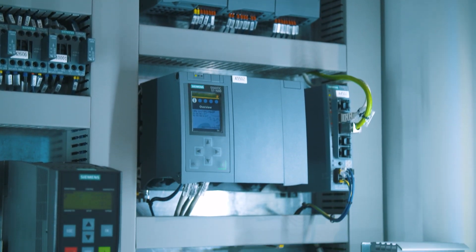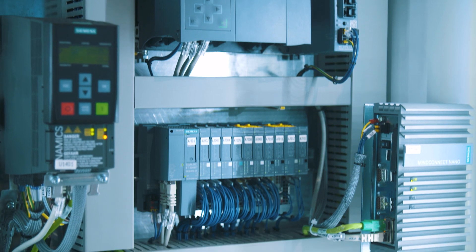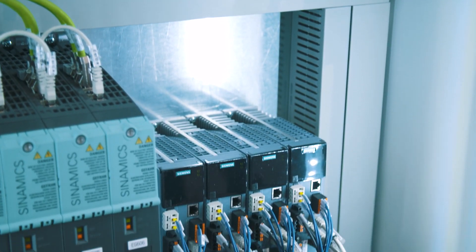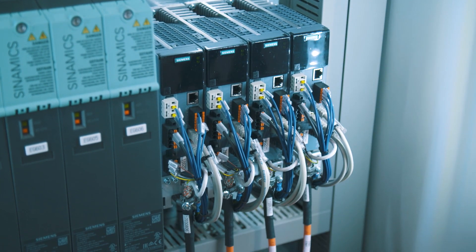The subordinate Simatic S7-1500 control and/or S7-1500 CPU technology assume the entire motion control functionality. ProfiNet IRT is responsible for the communication between Cymatic and Sinamics S210, including the control of the safety functions integrated in the drive, such as SafeTorque OFF and SafeStop 1 via ProfiSafe.